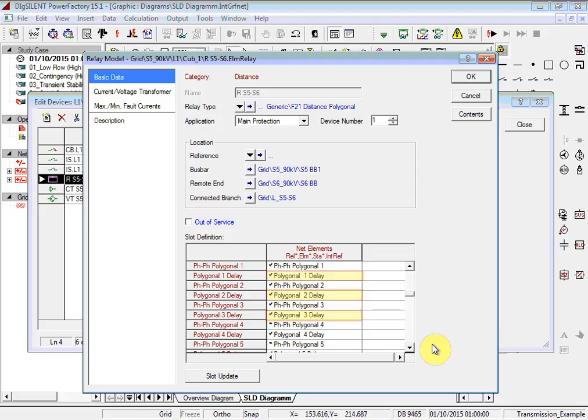For this particular relay type, time delays are assigned using the illustrated blocks. Phase-to-phase element settings are calculated, as well as phase-to-earth element settings. In addition, overreach zone settings may be calculated, although in this particular case there is no overreach zone in the relay. Select OK to return to the network.